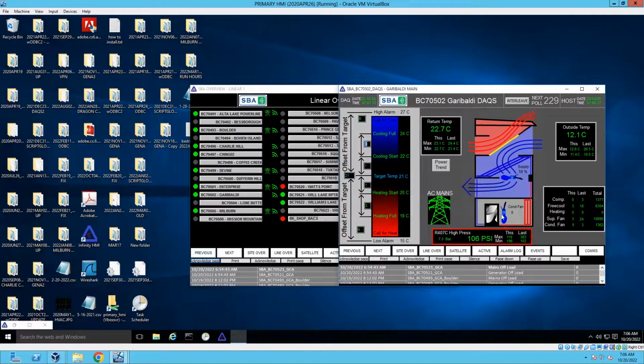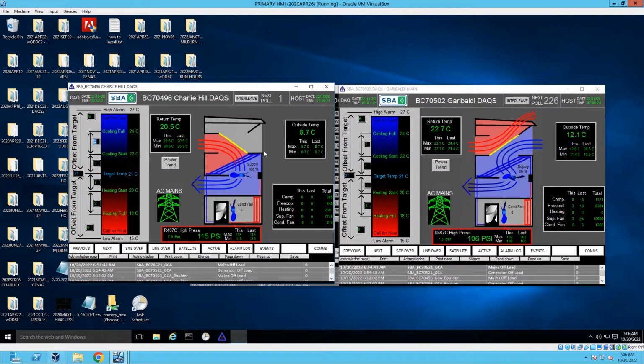If the free air cooling capacity cannot keep up with the load, then it reverts to DX cooling to attain the target temperature. In DX cooling, refrigerant is compressed in a power-hungry compressor, where it picks up heat. The hot refrigerant crosses an outdoor condenser coil, where a fan pushes outdoor air across it to cool it down. The refrigerant then crosses a thermal expansion valve, or orifice, to drop the temperature drastically through the pressure change. Then it enters the evaporator coil.